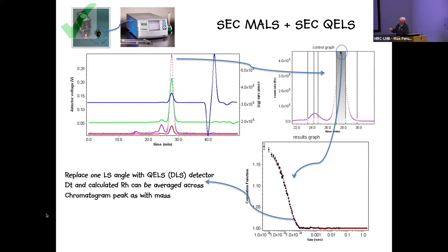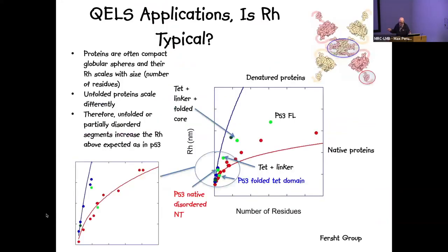Just as with static light scattering, we can couple DLS to size exclusion chromatography. We replace one of our 18 static light scattering detector angles with a dynamic light scattering detector, giving an additional chromatogram trace alongside refractive index, UV, and static light scattering. From every single point within the chromatogram where we have sufficient signal, we can get an autocorrelation function and thus the hydrodynamic radius.